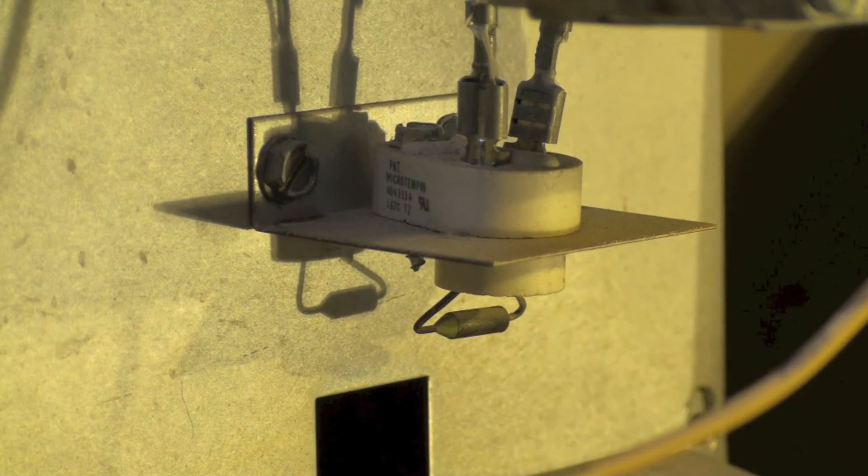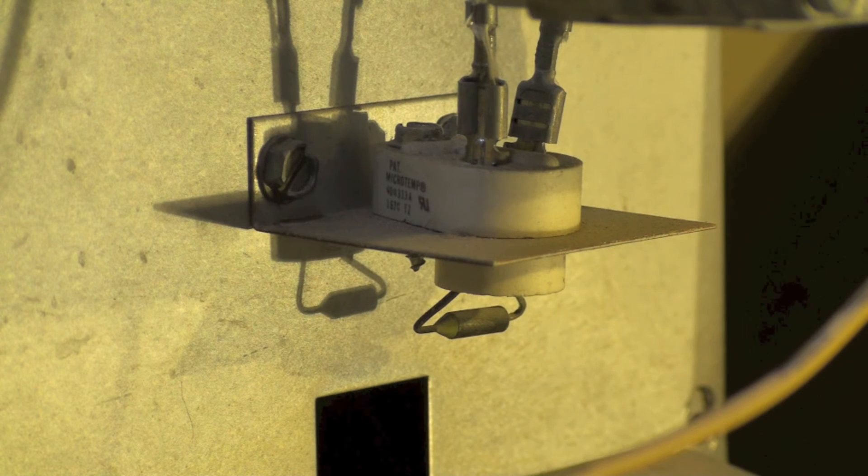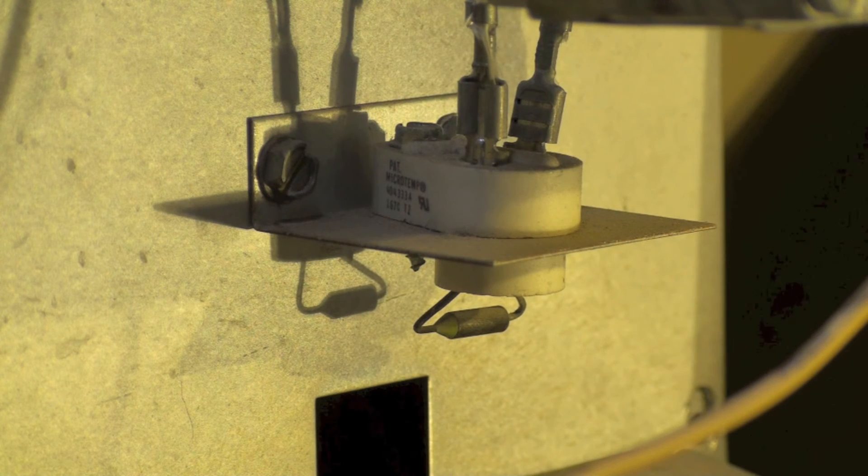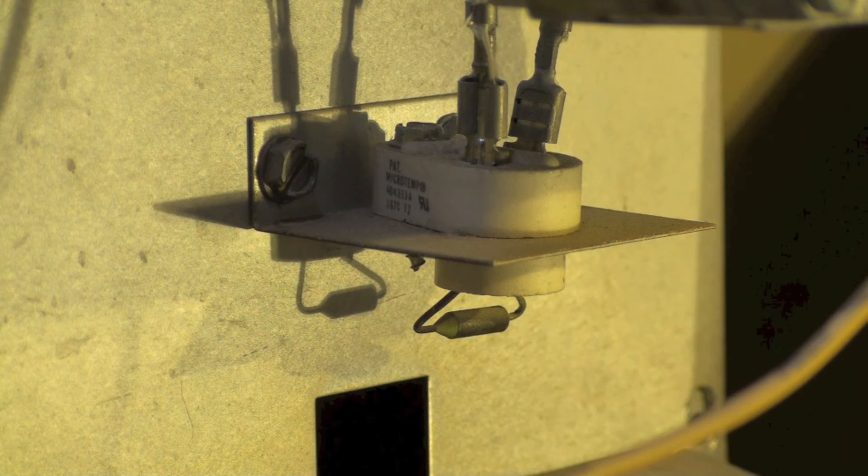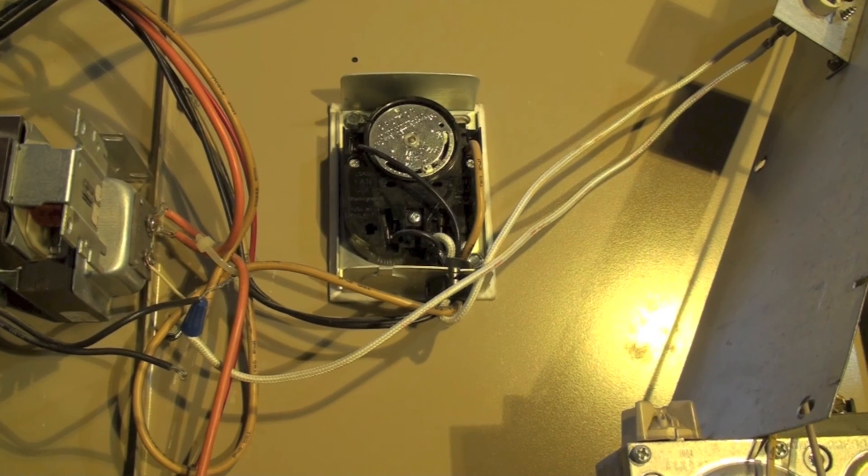That's a high temperature fuse. It gets about 300-some degrees and it will blow. Now it's a one-time fuse, so if it blows, that's time for somebody to come and take a look at this thing because it should not have rolled out flame out the front. So that's how that sequence works.